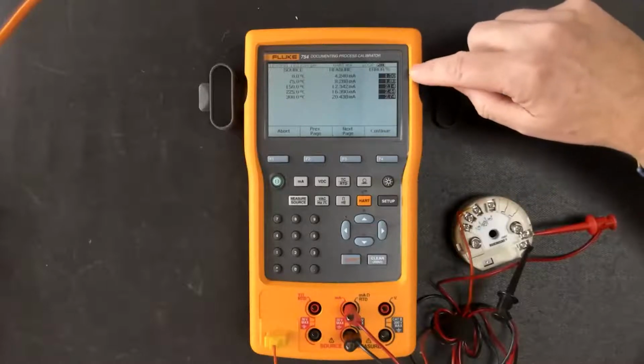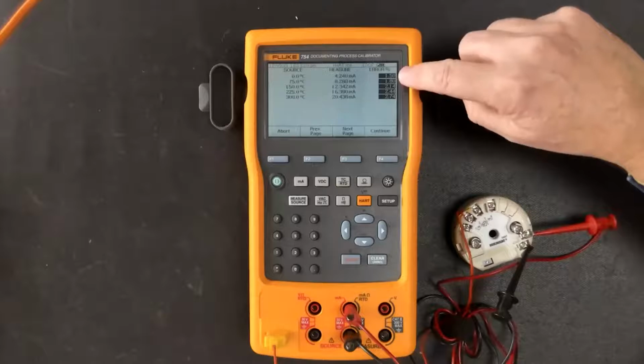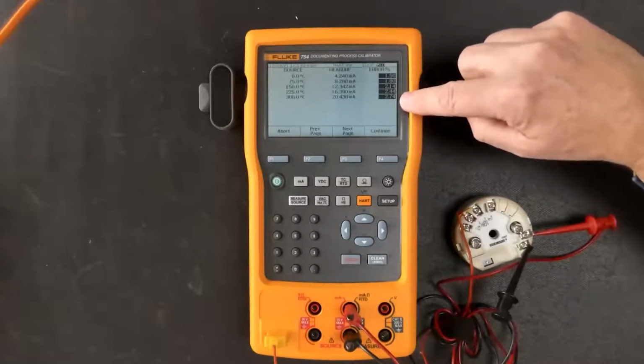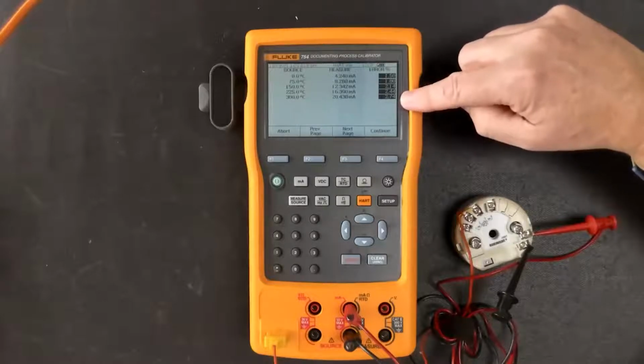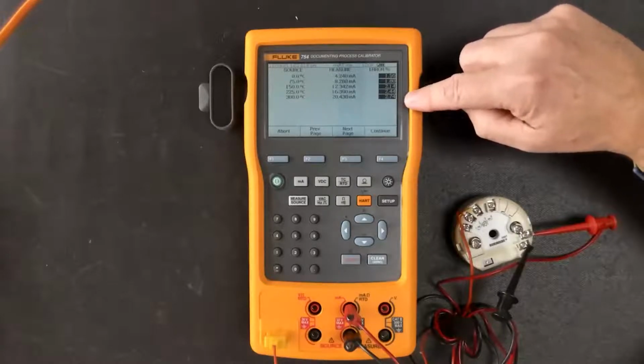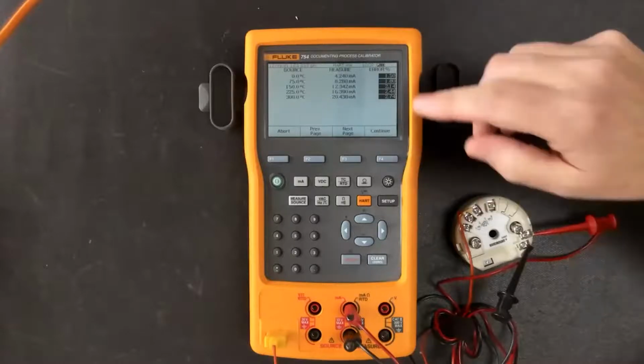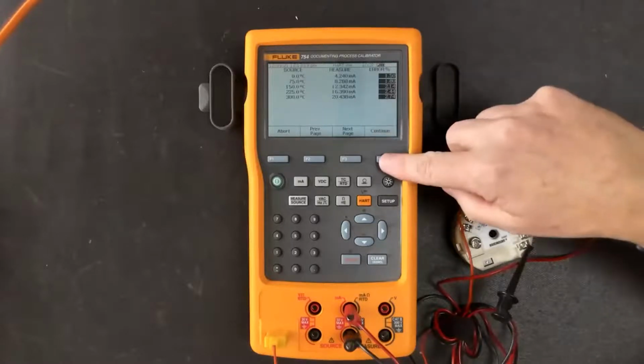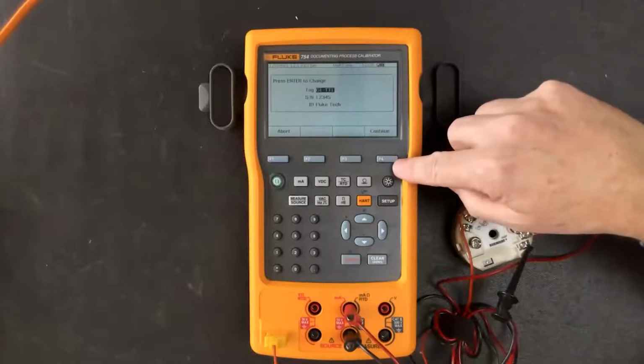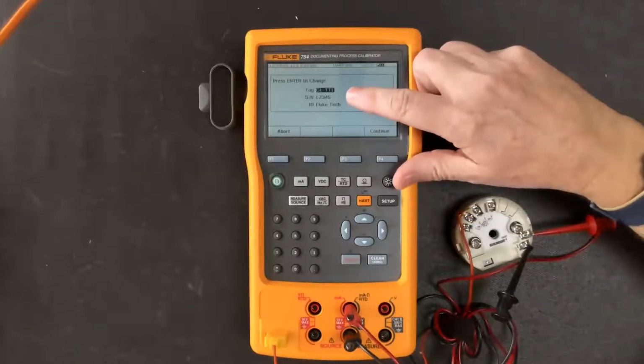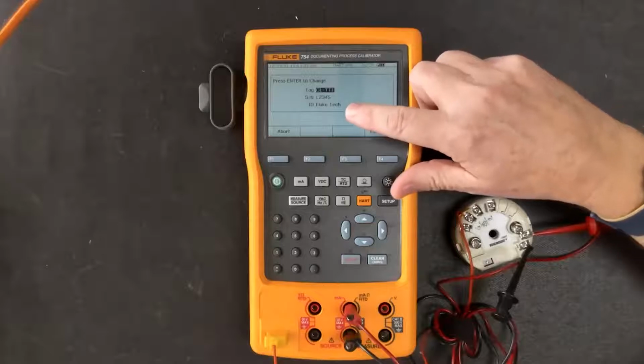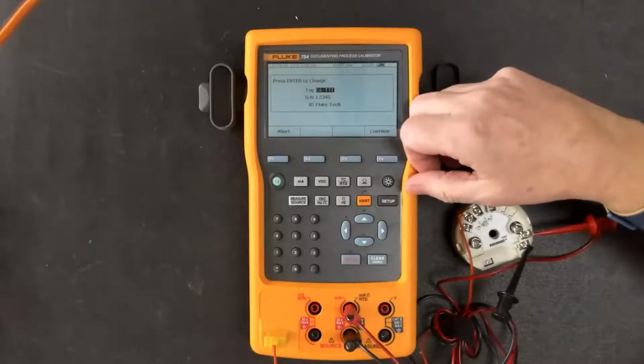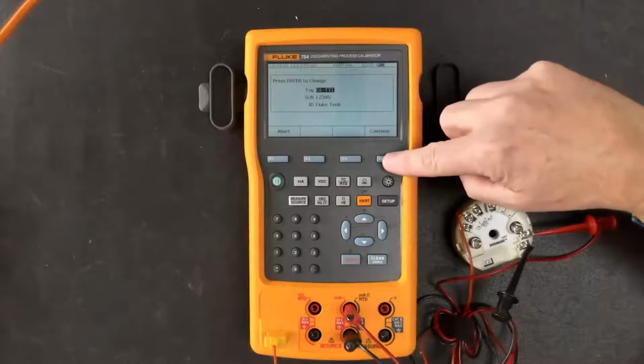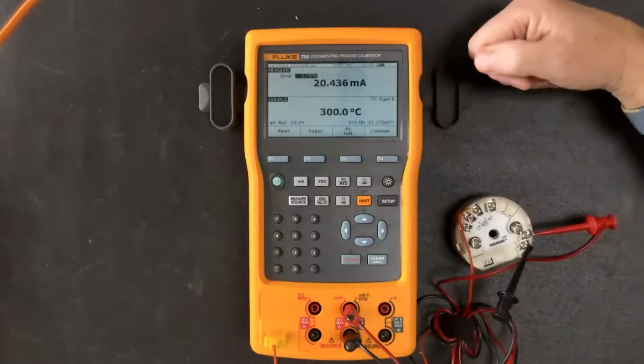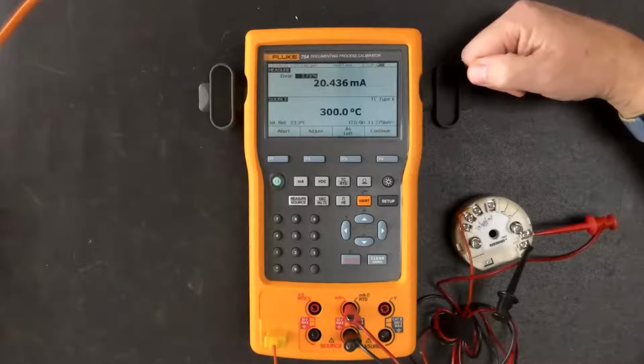And you'll notice, well, this transmitter is not in too good a shape. We got a lot of inverse video, which means it's out of spec. Remember, we had it set for 0.5% accuracy. We're over that right now. So what we're going to do is continue, and we've captured all this information in the calibrator. Now we've got the tag ID name. We're going to capture that, the serial number, and then the ID of the technician's name. Whoever did the test will be included. We'll continue. Now at this point, we know we're out of spec and we need to make some adjustments.